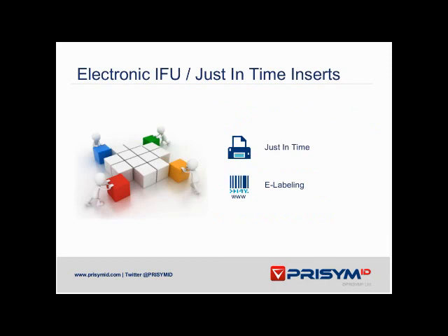And a solution, as the internet continues to play an increasing part in our daily life, regulatory bodies are increasingly comfortable with allowing end users to utilize the net. So in Europe, as we've talked about with Chris earlier, EIFU regulations allow the dissemination of electronic IFUs within the published guidelines. Effective global labeling solutions embrace these opportunities and can work hand in hand with your content management system to ensure that product changes that are implemented in operations are reflected on the website immediately.